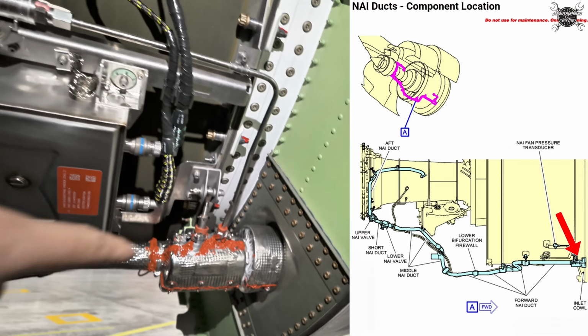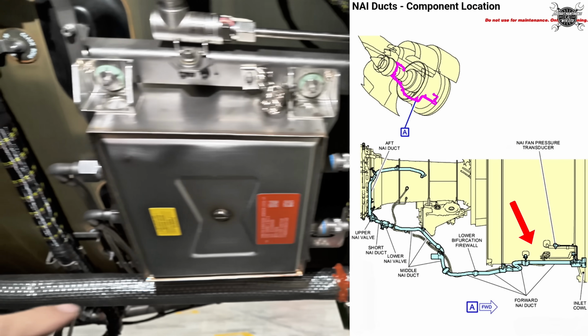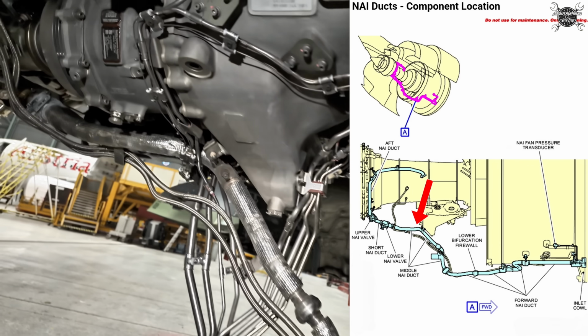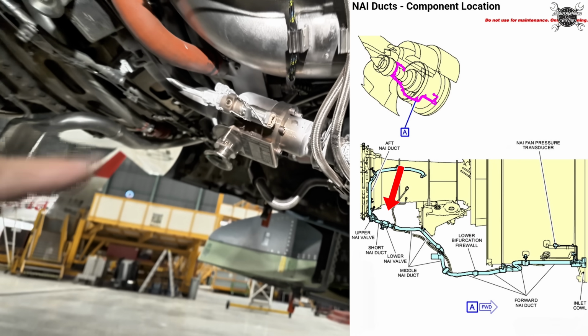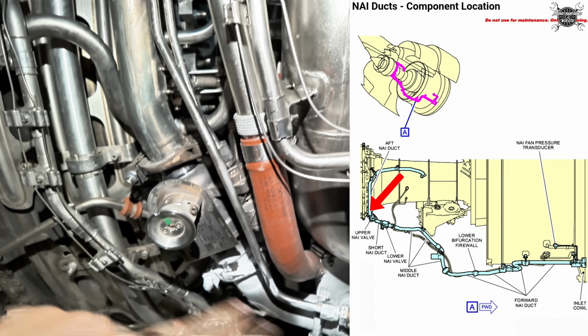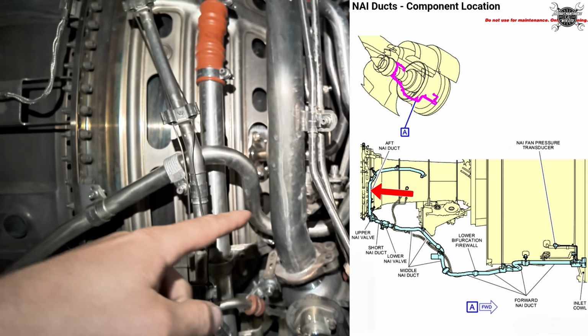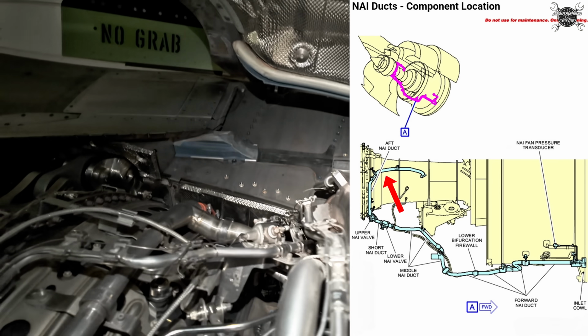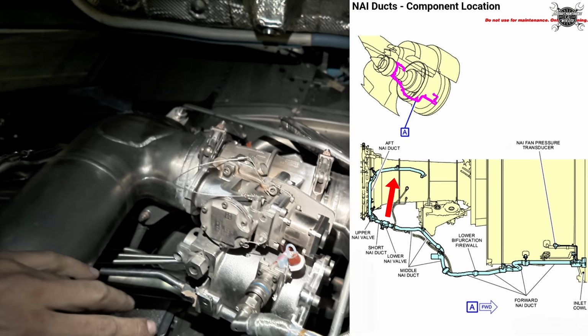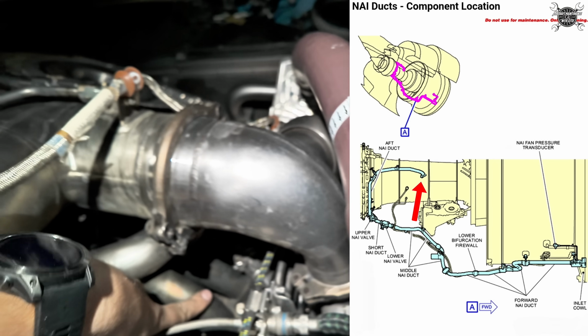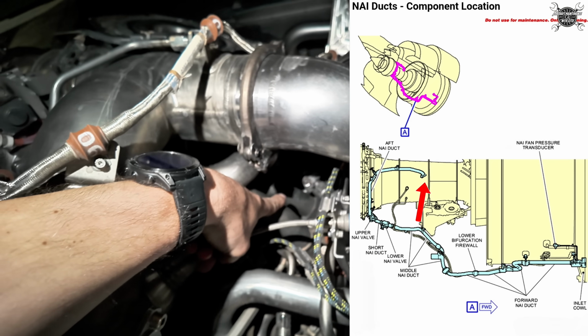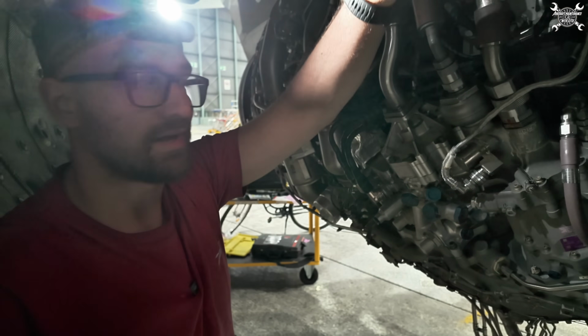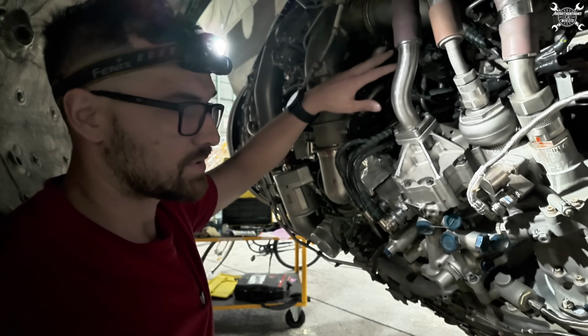Now we are behind the intake, and this is our anti-ice duct. Over here you can see a pressure transducer, but we'll follow the anti-ice duct, which goes inside of the core, and then we have the downstream anti-ice valve and the upstream anti-ice valve. We'll get to those valves a little bit later on, and then we follow the line all the way under the bleed components to the 6th stage of the high pressure compressor. So the bleed air for intake anti-ice is taken from the 6th stage of the high pressure compressor.